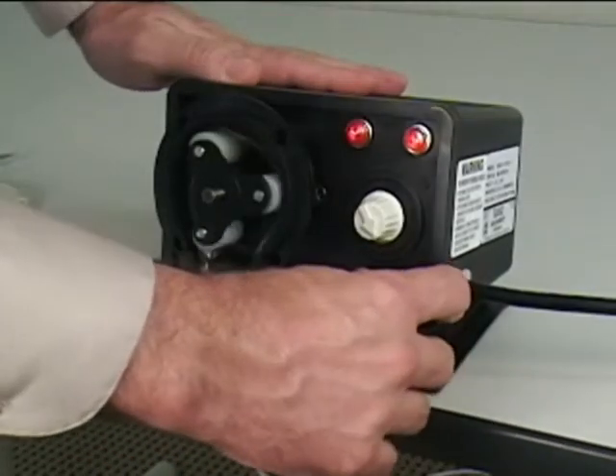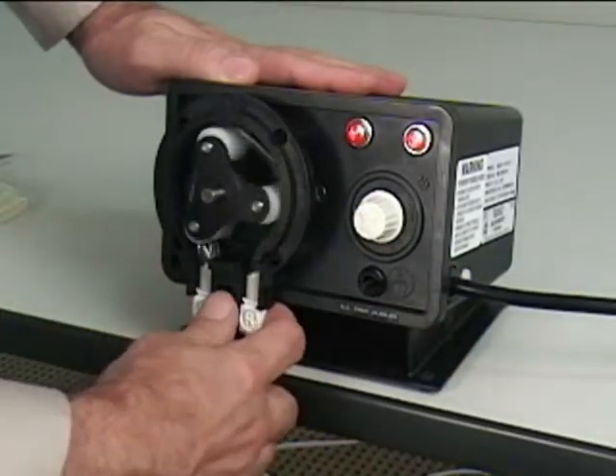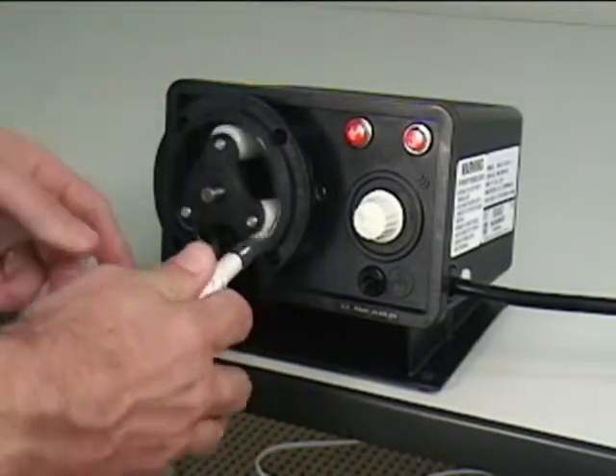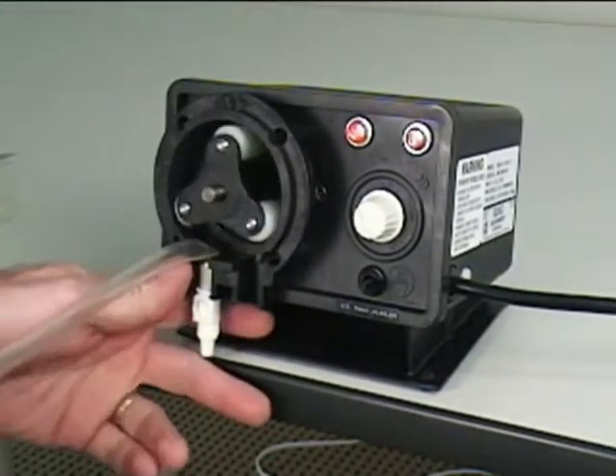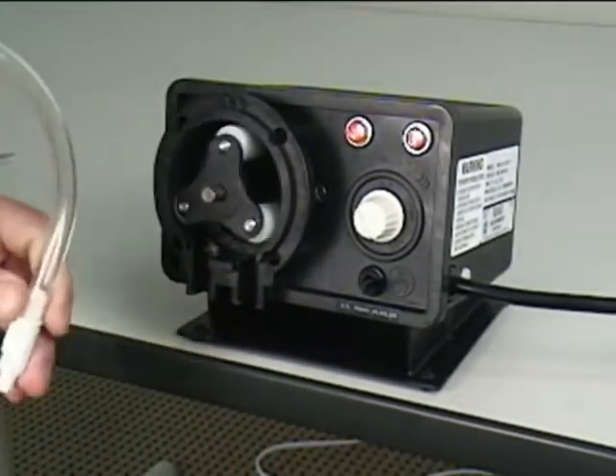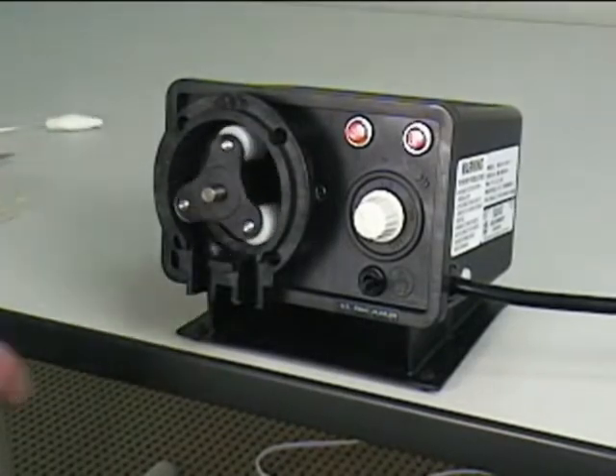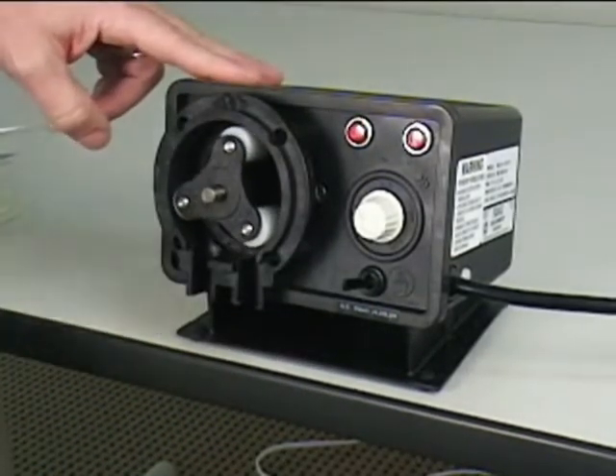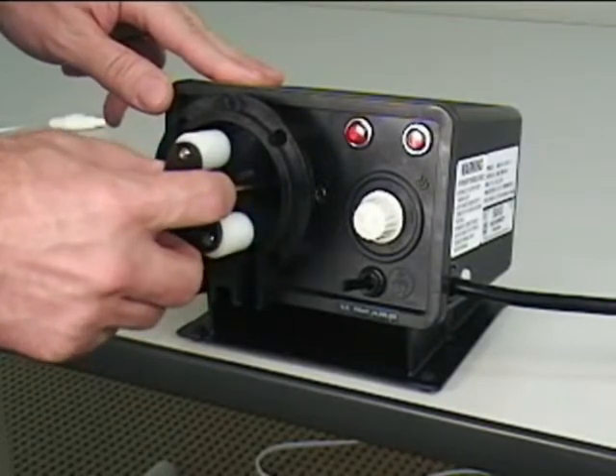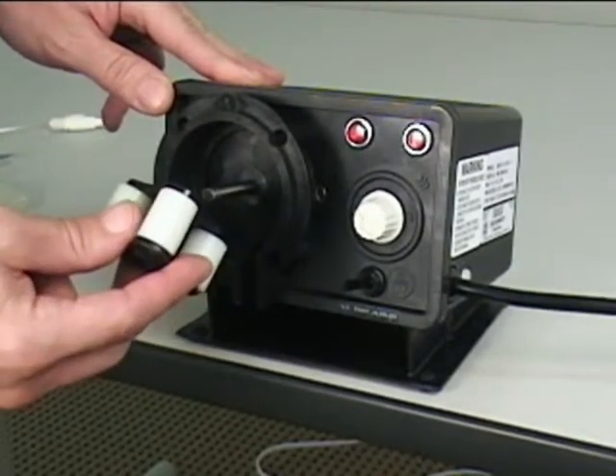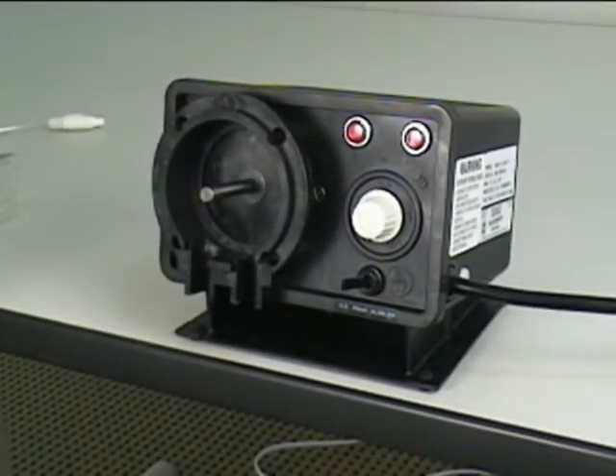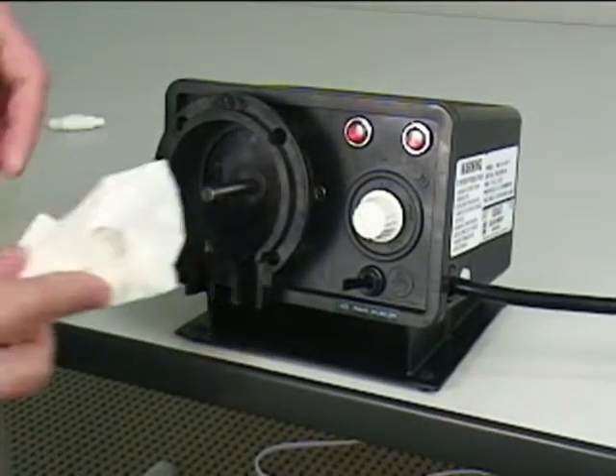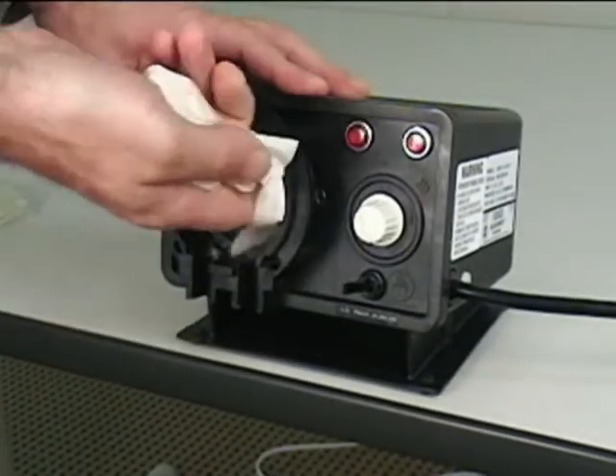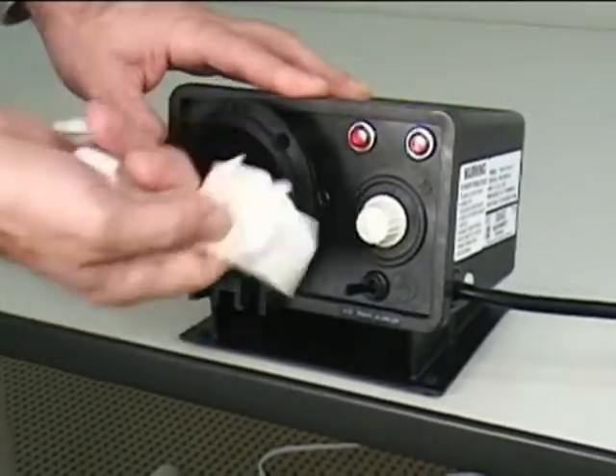The pump must be running to remove the old tube. Be careful to keep your fingers out of the pump head. With the pump running, grasp the inlet side of the pump tube and pull straight out. Carefully guide the tube out of the head. While continuing to hold the tube, pull the outlet side of the tube straight out. The pump head and roller assembly must be cleaned before installing the new pump tube.